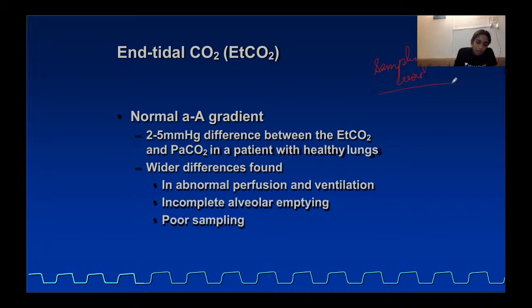So now, where all can these sampling errors occur? One is at the HME filter. At the HME filter, there is a small port where this gas sampling line can be attached. When this gas sampling line is placed, it is usually placed on the machine side of the HME to avoid contamination and waterlogging. So this is the patient, the ET tube comes, and over here there will be an HME filter.